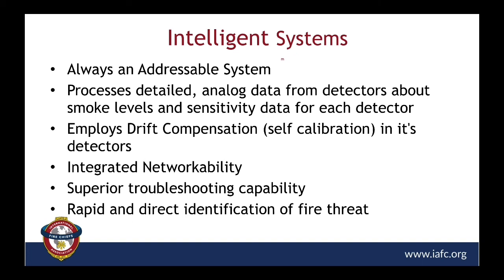If you take that detector down from the ceiling, you're going to get a trouble condition. If you remove a pull station or knock a pull station off the wall with a baseball bat, you're going to get a trouble condition. And this is going to be able to pinpoint where that trouble is coming from. Conventional systems will tell you you'll have a problem in the building for the most part. An addressable intelligence system will let you know that you have a problem on this pair of wires, probably in this location, in either one or two or three different offices.